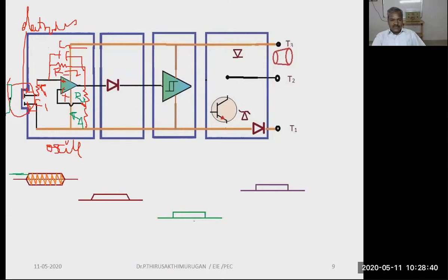When the object approaches, nearing the sensor head, oscillations are generated. So this is the oscillation generated as the object is nearing. Then when the object is on the sensor head, more resonance frequency is generated in the capacitive probe. Except for this, the other things are diode D1. This is the demodulator oscillator stage. This is the triggering stage, that is the Schmitt trigger stage. This is the output stage. The remaining things are the same.